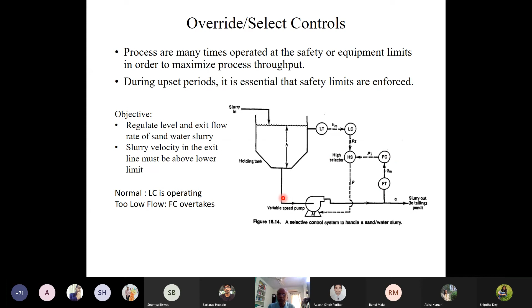So we'll have a flow controller. The flow controller has a set point, which basically ensures that this flow has to be there. Here also the level controller has a set point, and as the level falls, this level controller output will decrease, and at some point, when it falls below the output of this one, the high selector switch will take the output of this flow controller, not the level controller. So normally this control loop will work, but during the upset period or for safety limitations, this controller will work. So this is basically override control.